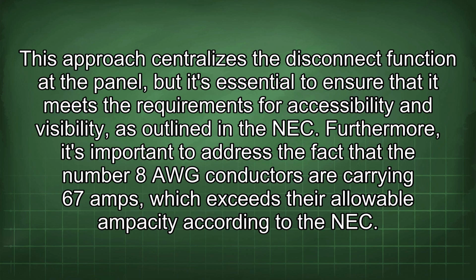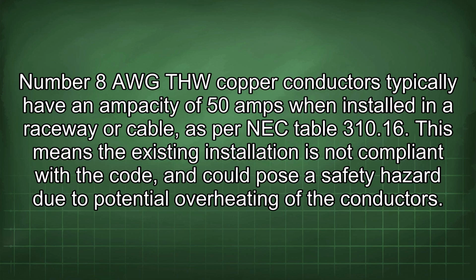Furthermore, it's important to address the fact that the number 8 AWG conductors are carrying 67 amps, which exceeds their allowable ampacity according to the NEC. Number 8 AWG THW copper conductors typically have an ampacity of 50 amps when installed in a raceway or cable, as per NEC Table 310.16. This means the existing installation is not compliant with the code and could pose a safety hazard due to potential overheating of the conductors.